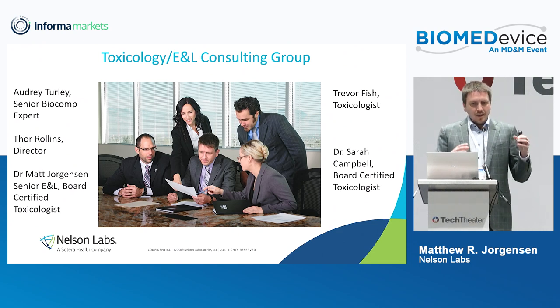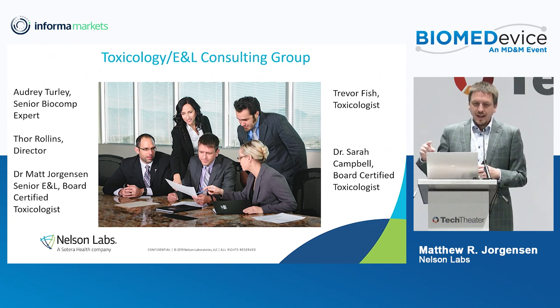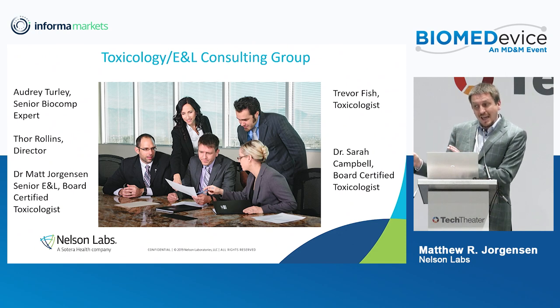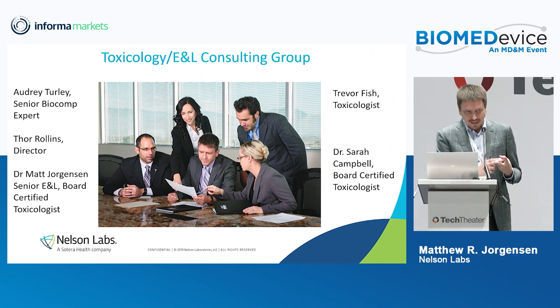It used to be that biocompatibility experts, chemists, and toxicologists were siloed — they didn't really need to talk to each other to be successful. When you have independent groups, a biocompatibility expert might say genotoxicity testing is required, and a chemist who has never talked to that expert does a chemistry study without knowing it's for genotoxicity evaluation, gives that data to a toxicologist who then says this chemistry study isn't good enough. That type of thing just won't get through the FDA anymore. The way to evaluate through this process really requires a team effort — at a minimum, a biocompatibility expert, a chemist, and a toxicologist all talking to each other in the planning phase.